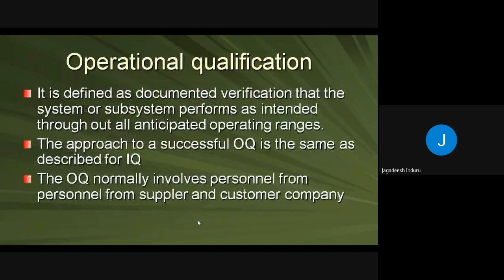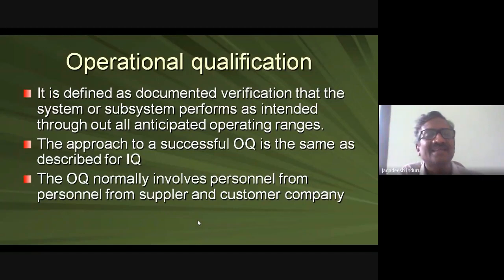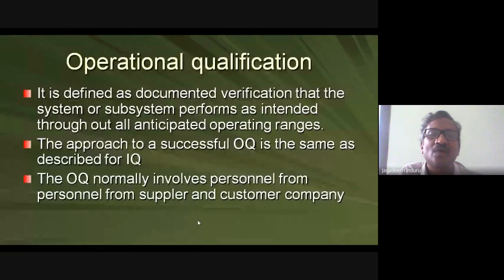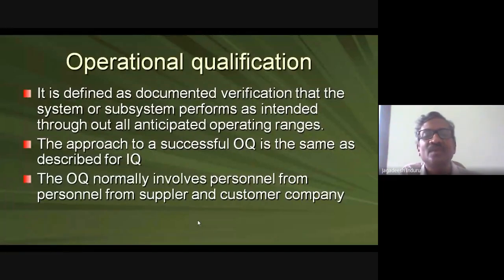Operational Qualification (OQ) is defined as documentary verification — comparing a predetermined document against reality — that the system or subsystem performs as intended throughout the anticipated operating ranges. For example, in a tray dryer (the system), the fan and coils are subsystems, and the vacuum pump is another subsystem. If you want to operate the dryer from 40°C to 200°C, you check whether it works consistently at both limits.